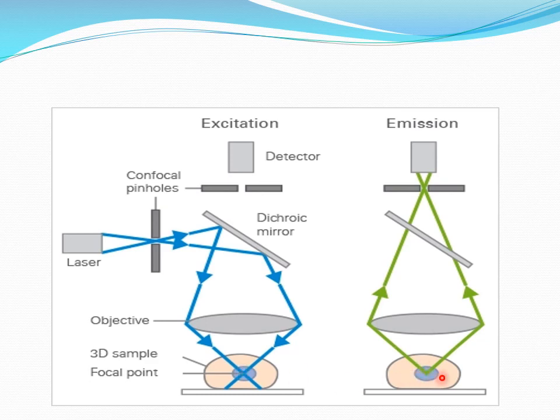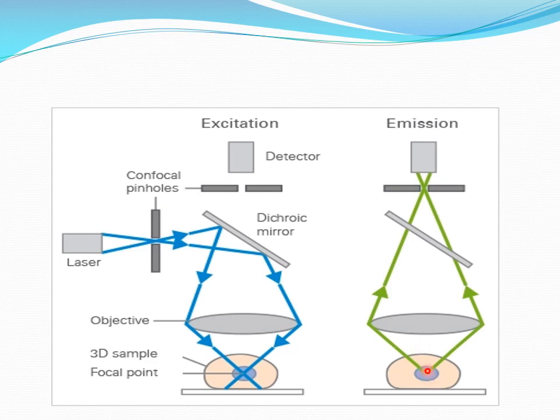At the point of interest, the fluorophores emit fluorescence. When light energy is emitted from a focus, it moves out and the objective focuses it back onto a point. At this confocal point — confocal meaning having the same focus — the focus of the point of interest and of the pinhole filter placed in front of the detector is the same. This is the basic principle of confocal microscopy.